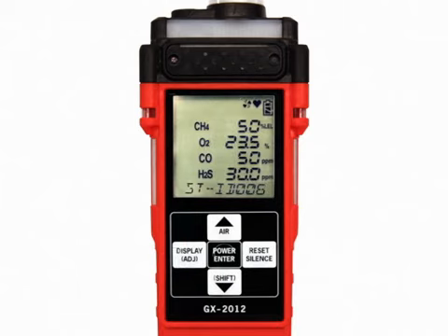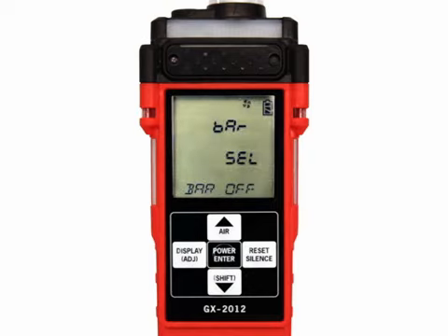The gas readings that were taken during the snap log are displayed, and the station ID that was in use during the snap log is displayed along the bottom of the screen. You can use the Air and Shift buttons to scroll through the different snap logs. The gas readings and station ID will change, but the snap log ID is not visible from this screen. If you wish to scroll through the different snap log IDs, you must press and release the Display Adjust button to return to the snap log screen and re-enter. Press and release the Display Adjust button again to proceed to the Peak Bar Select screen.